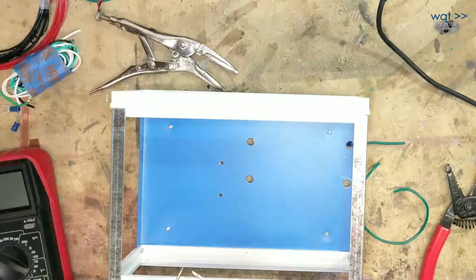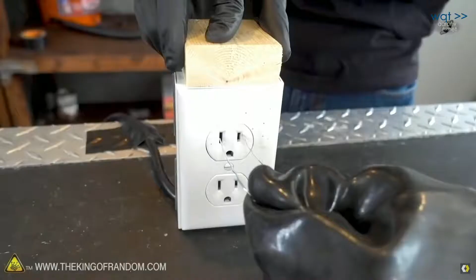Good. The reason this is important is for two reasons actually. One is for short circuits. If a 120 volt wire gets loose in here and touches a metal piece somewhere, you don't want that metal piece to be isolated from the ground, which is coming in on the socket back here. And I'll also make a nice big fat star on one of the transformer legs, because the transformer is the largest potential source of fault current. In fact, if you get a fault in the primary winding of the transformer, it'll be pretty much like putting a pair of keys or a screwdriver right across the mains.